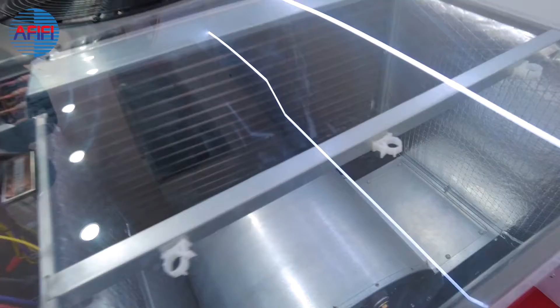You get higher efficiency because you have fewer moving components. Higher COP, exactly. That's what everybody's targeting, and fewer components as well. So you're saying a single compressor 10 ton has higher COP compared to dual compressor? Right. The single compressor 10 ton one that Emerson now offers is one module. The smallest size is 25 kilowatt for the modular. In ton language, 25 kilowatt is like 7 tons, 7.5, something like that.